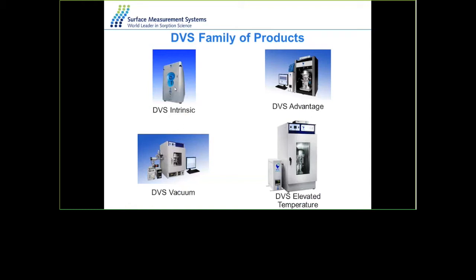There are different versions of the system available. The DVS Intrinsic has a temperature range of 20 to 40°C and does water only. The DVS Advantage does both water and organic vapors with a temperature range of 5 to 60°C, and can be connected to a Raman spectrometer. The DVS Elevated Temperature system goes from 20°C to higher temperatures, with a standard preheater up to 200°C and an optional high-temperature preheater up to 300°C.